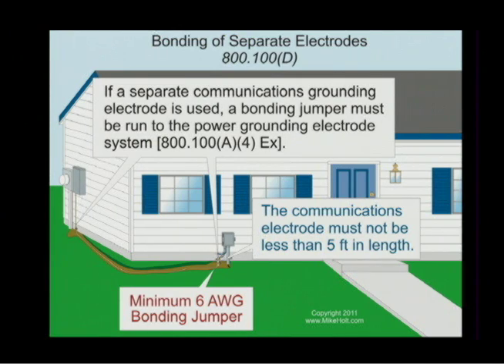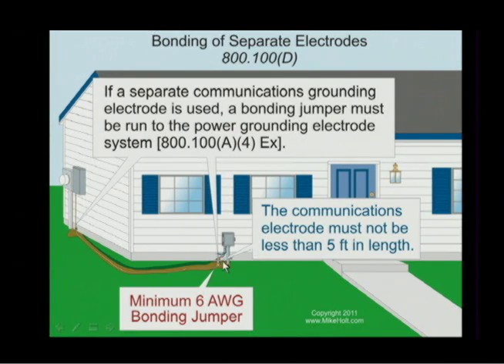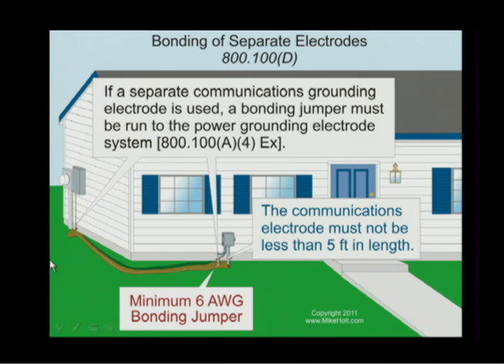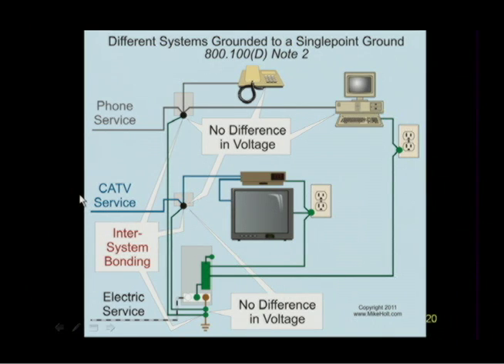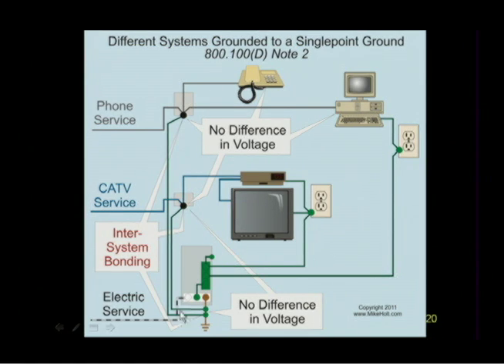Section 800.100.D says that when you drive a ground rod for a communication system under Article 800, you have to bond them together with a 6 AWG wire. When your grounding conductor run is more than 20 feet, you have no choice — you drive a ground rod. The length of the ground rod is no less than five feet. Then bond them together with 6 AWG wire. Best practice is to get the entry point as close as possible to the AC service to limit the length of the bonding conductor to the inter-system bonding terminal. The goal in 800.100.D is to bring all systems to the inter-system bonding terminal to reduce the difference of potential between systems, as covered back in 250.94.